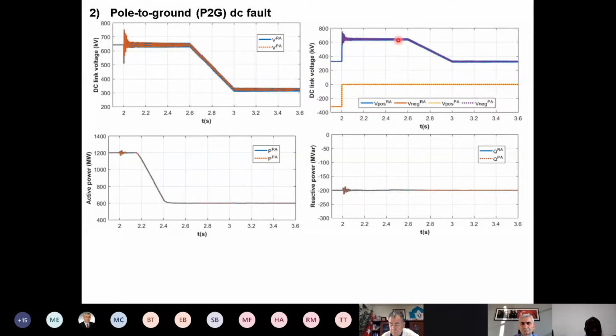If you allow that to happen for a long time, the DC cable will explode. So what we have done here, we instructed the converter to reduce the DC voltage to half. And you can see here now the fault still exists, but we're operating with VDC at half. But before we activate these actions, we have to reduce the active power to half. So from here we go from 1200 megawatt to 600 megawatt.